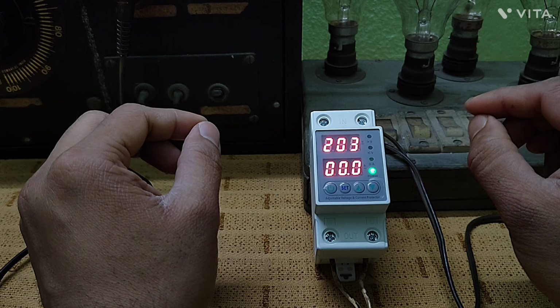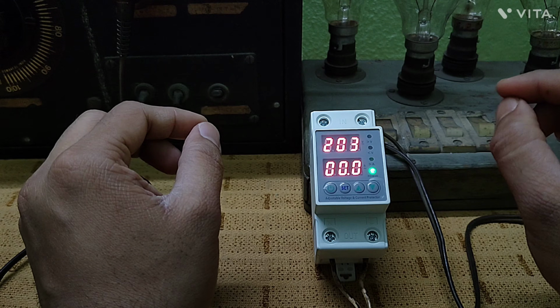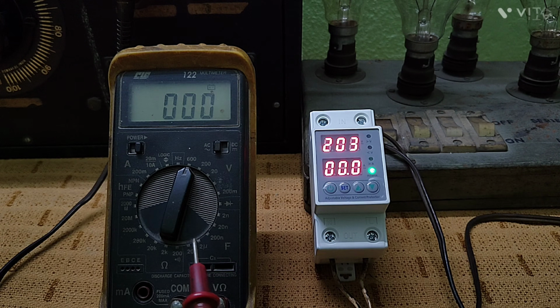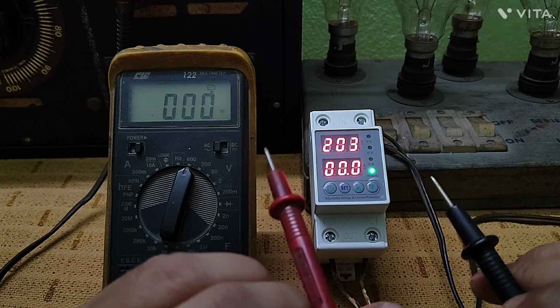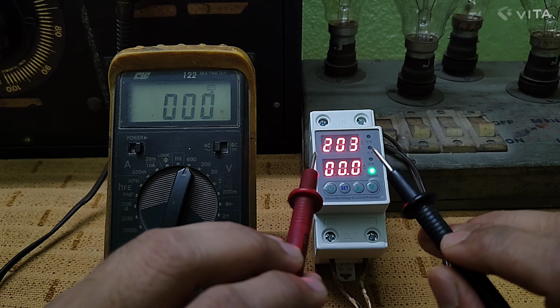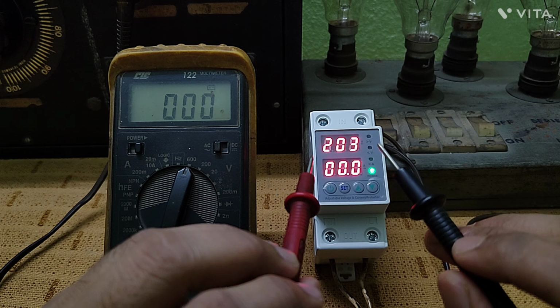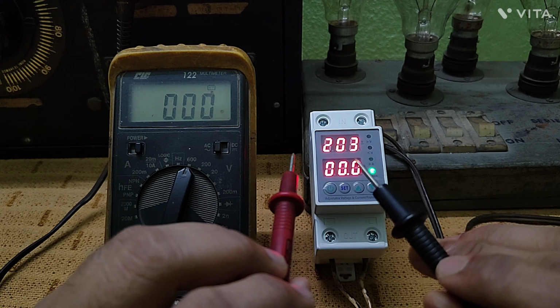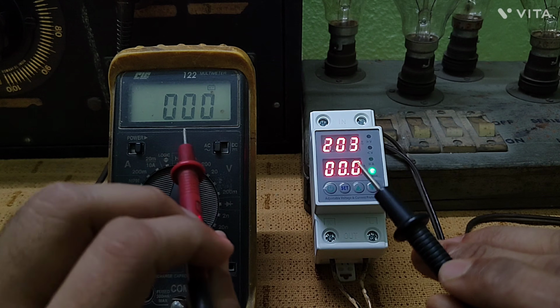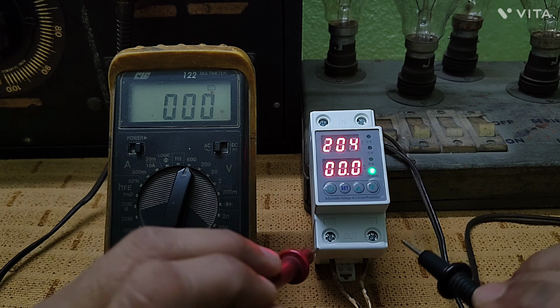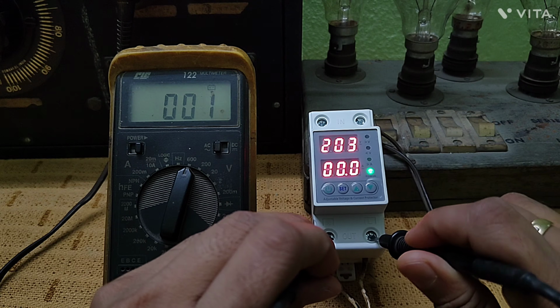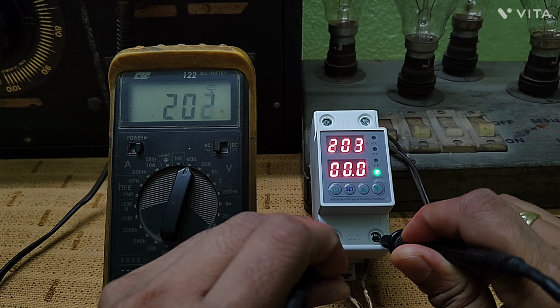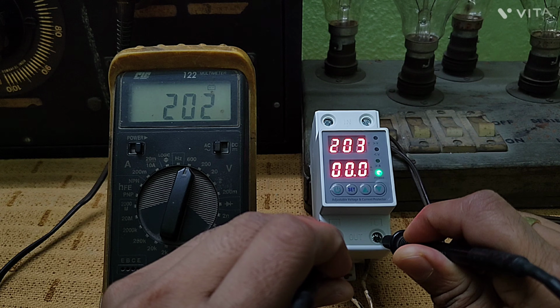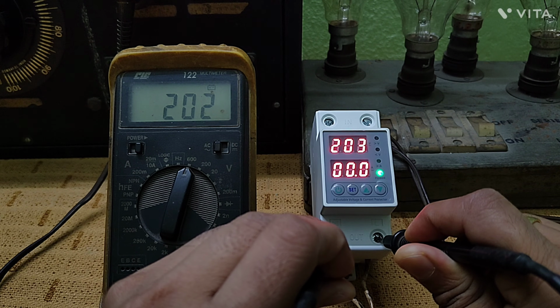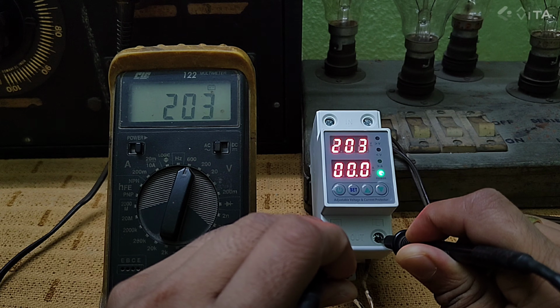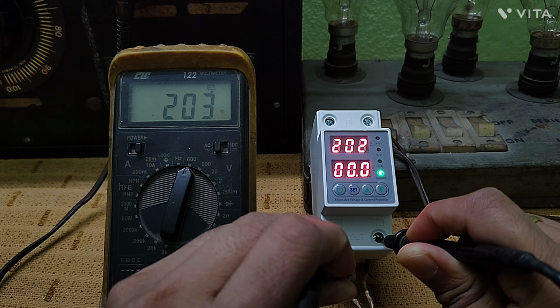Now I'll do a voltage calibration check to see whether my device is accurate or not. So I have my multimeter with me. As you see, this device is showing 203 volts, and I set minus 1.5 to make the voltage calibration match this multimeter. Now let's see what the voltage is. I just place the terminals over there. You see, it's quite accurate - 203 is shown in this particular device and 202 in my multimeter. It's 203. That's it. So the voltage calibration is done.